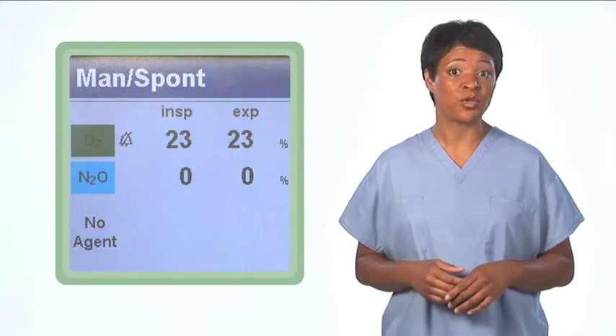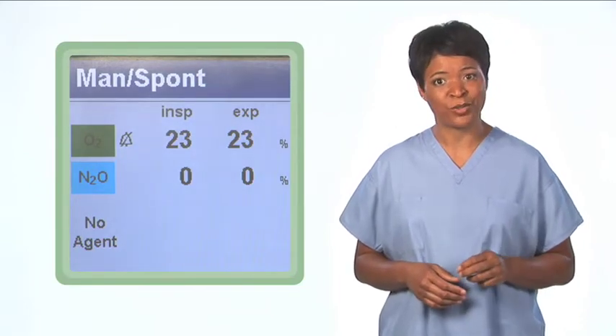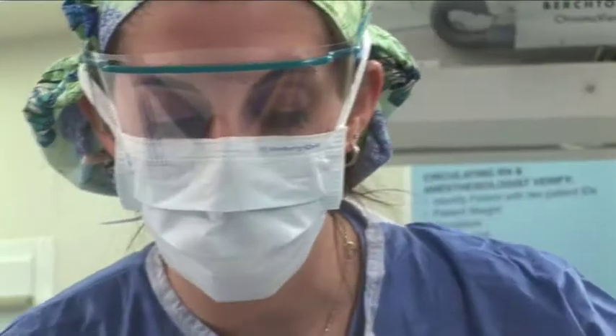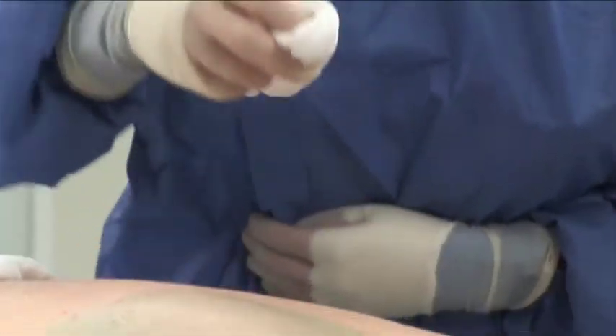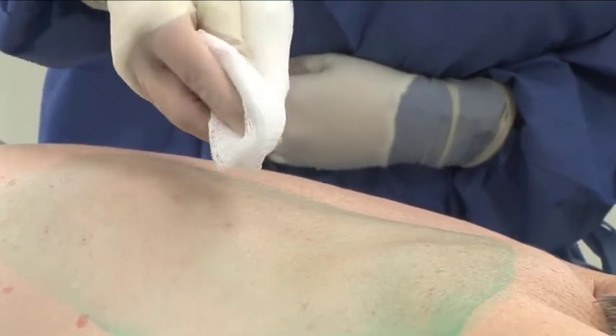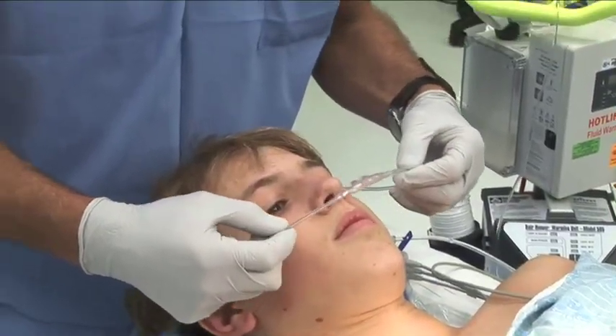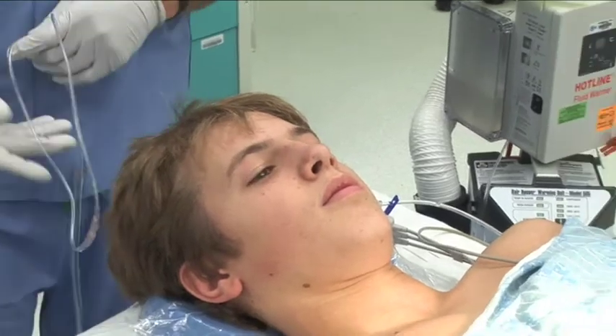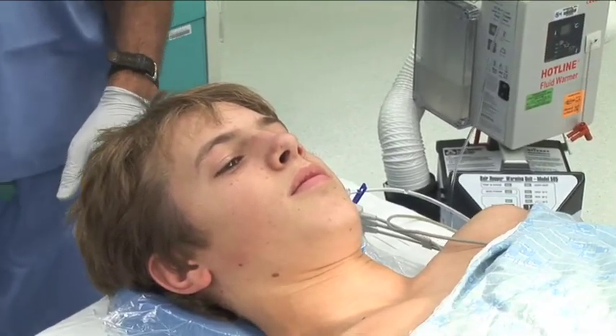Inspired and expired oxygen monitoring will confirm the desired concentration. High gas flow should allow for rapid reduction of oxygen concentration to facilitate surgery, and rapid increase in oxygen concentration to avoid prolonged hypoxia. Surgical fires are preventable. The risk of surgical fire should be discussed by the operating room team. If an alcohol prep solution is used, it must be allowed to dry completely before draping. Open oxygen administration for surgery of the head, face, neck, and upper chest is not recommended.